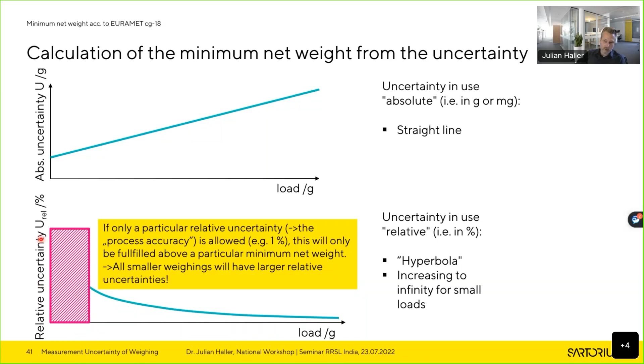And this is also shown on our calibration certificates. This is more or less the same diagram as I've shown here before, the relative uncertainty over the weighing range. The difference is just that this is a double logarithmic plot, because otherwise you would hardly see anything on that diagram. But what you can do now, and this is usually also given as an example on our calibration certificates, is say, I do not want the relative uncertainty to be bigger than 1%, so you just follow this line to the relative uncertainty, which is this green-blue line. Or if you say, I want to multiply the uncertainty with an additional safety factor, which is quite common, of 2, 3, 5, or 10, then you have to go to the respective colored line.